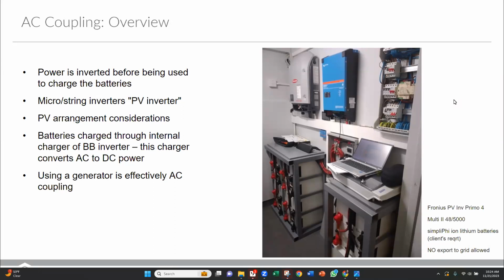So what we've done here is we've come into an existing site, and there are many, many sites out there that have existing grid-tied inverters. Now people want backup. So the concept here is that we can come in and add a battery-based inverter, and if the grid goes down, that battery-based inverter is going to continue to create a grid in the home. And as far as that Fronius is concerned, it sees grid and it's going to keep doing its thing. So why we AC couple here is that we can go back and reach out to the existing customers that you've already done work for, and offer them that battery backup solution.